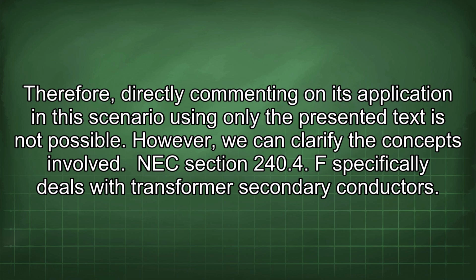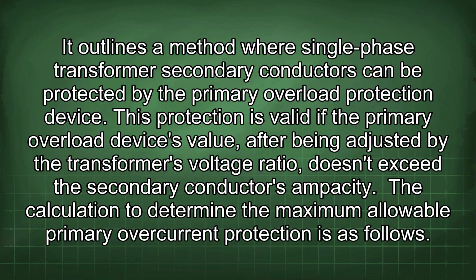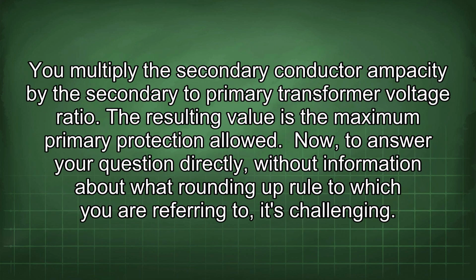NEC section 240.4(F) specifically deals with transformer secondary conductors. It outlines a method where single-phase transformer secondary conductors can be protected by the primary overload protection device. This protection is valid if the primary overload device's value, after being adjusted by the transformer's voltage ratio, doesn't exceed the secondary conductor's ampacity. The calculation to determine the maximum allowable primary overcurrent protection is as follows. You multiply the secondary conductor ampacity by the secondary to primary transformer voltage ratio. The resulting value is the maximum primary protection allowed.